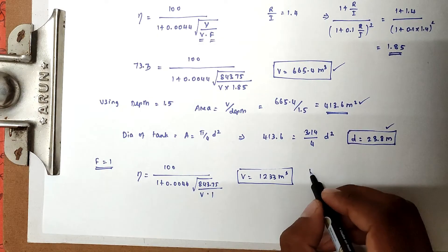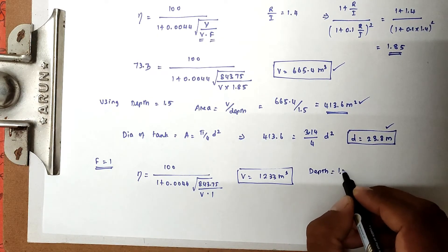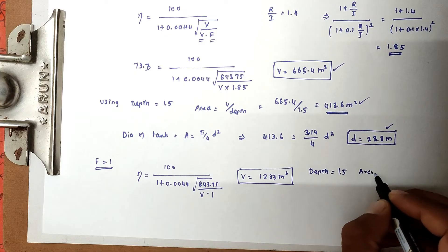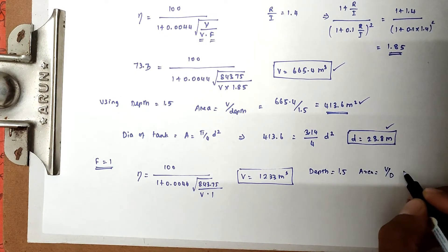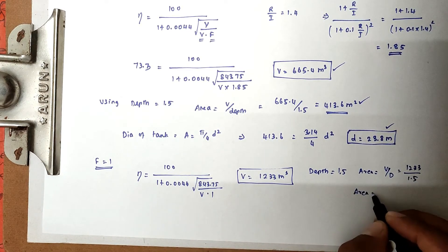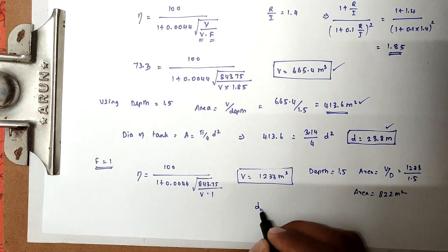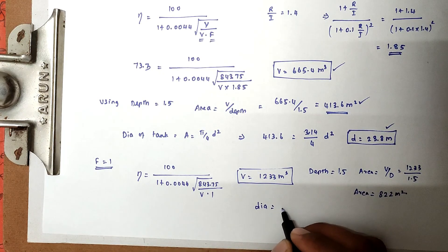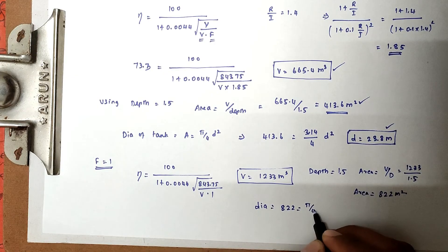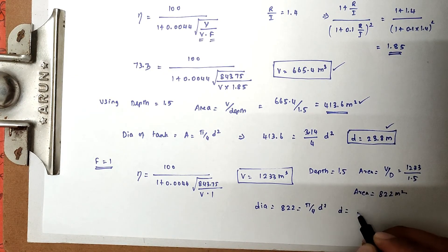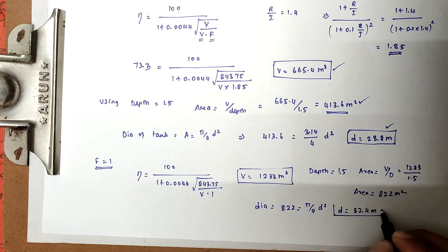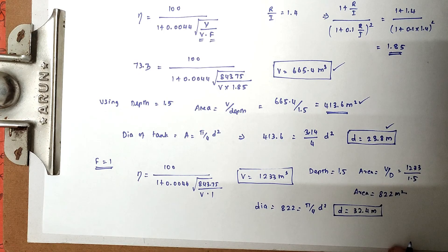Using the same depth of 1.5 m, area equals 1,233 / 1.5 = 822 m². From area = π/4 × D²: 822 = 3.14/4 × D², so D = 32.4 meters. This is the final answer for the standard rate trickling filter. This is the method to solve trickling filter problems. Thank you.